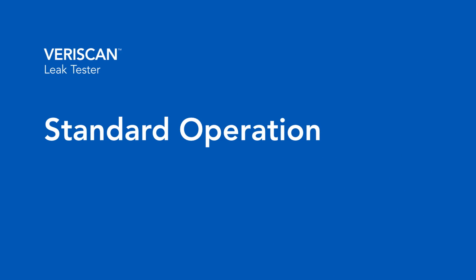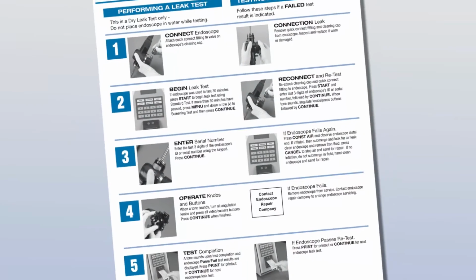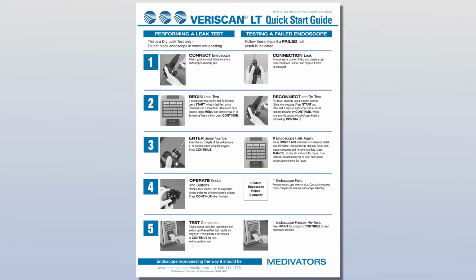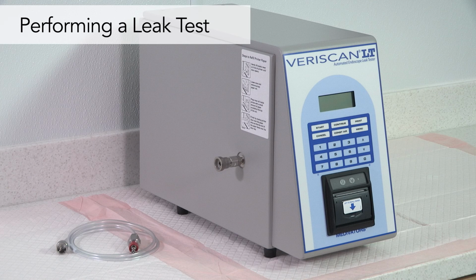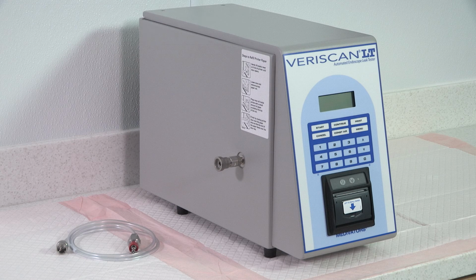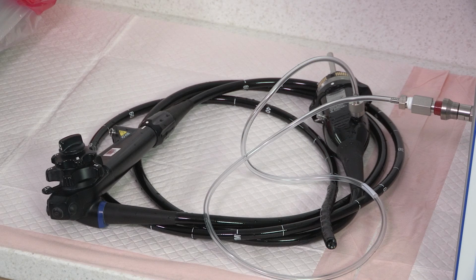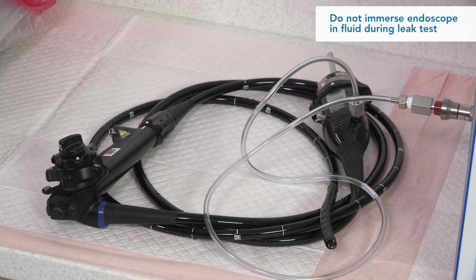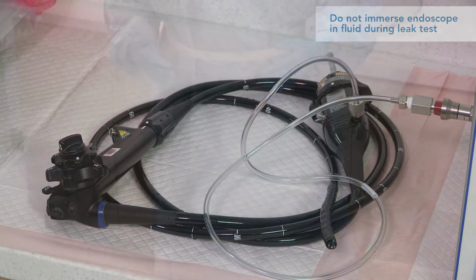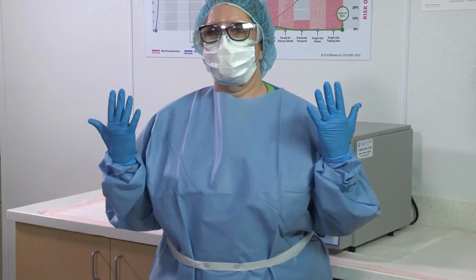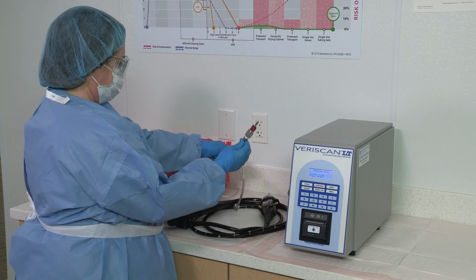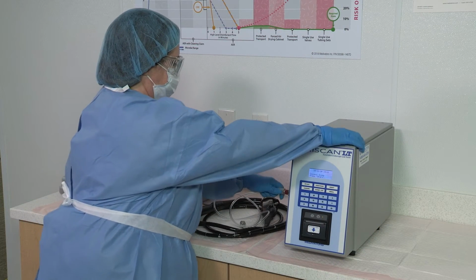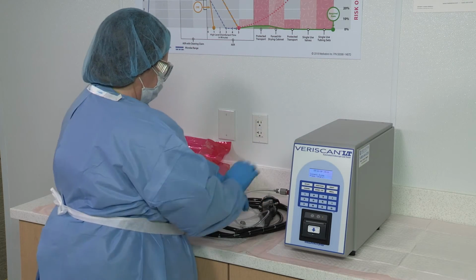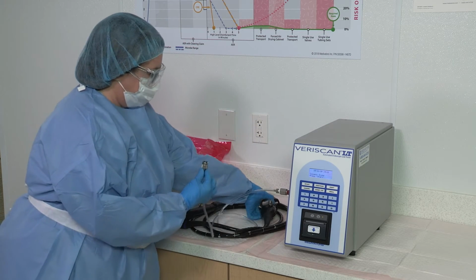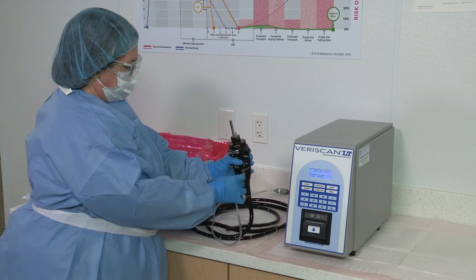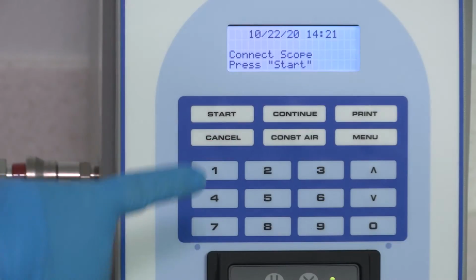Let's walk through standard operation of the VERISCAN Leak Tester. For quick reference, use the Quick Start guide supplied with the unit. We'll begin by performing a leak test. It is important to remember that the VERISCAN Leak Tester performs a dry leak test. Do not place or immerse the endoscope in any type of fluid while performing the leak test. Don the facility-required PPE. To begin, connect the quick connect tubing to the VERISCAN Leak Tester. Then connect the endoscope. Press Start on the touchpad.